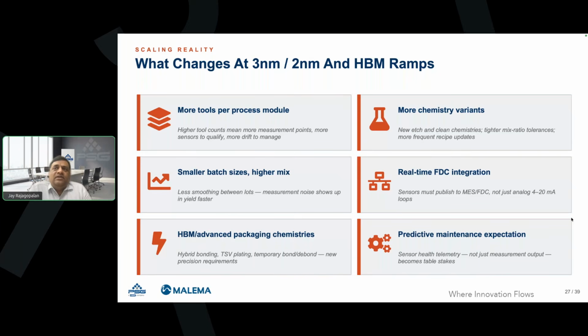And real-time data integration. For example, if you just measure flow and the flow meter produces 4 to 20 milliampere or 0 to 10 volt output, just one variable. But nowadays, the advancements that are happening in the flow sensor technologies provide you more data about the health of the product, as well as additional variables like pressure and temperature in addition to the flow and density, for example. So such data cannot be transmitted by just two wires. So you need to have a digital communication using that same two wire, not by analog means. So predictive maintenance expectation also increases a lot with this concentration of so many products and process steps.